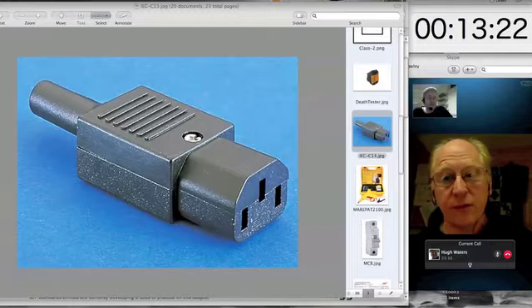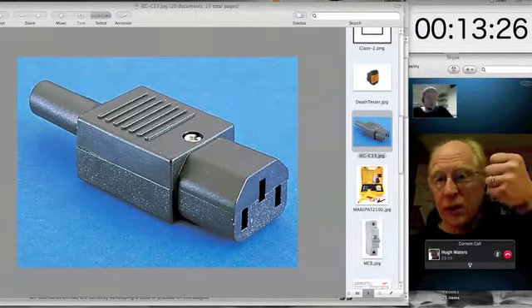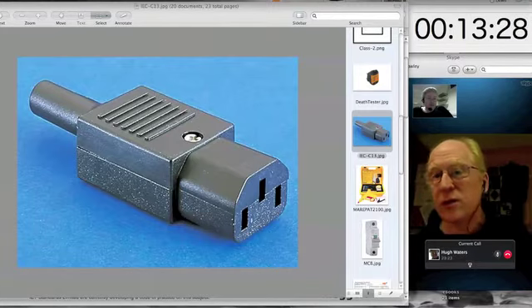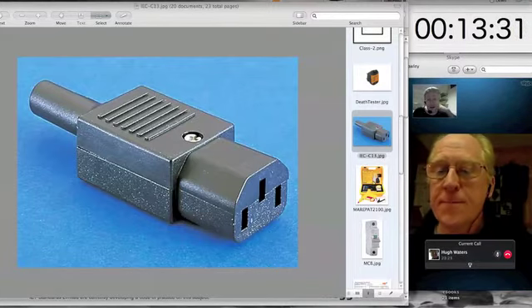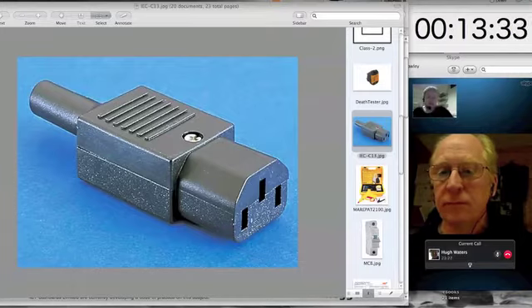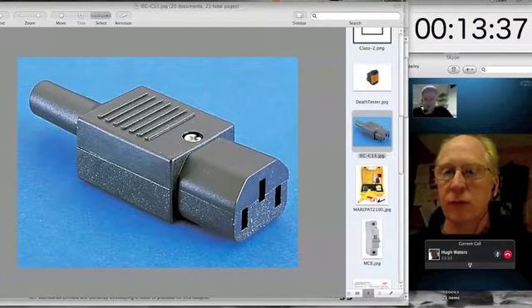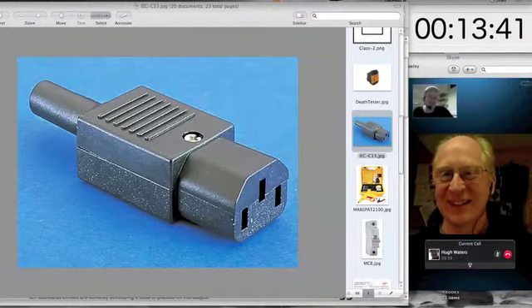Do they have MCBs to the bus bars, or do they still have those enormous fuses? They used to have one on each phase. Yeah, so if you can consider 3 200 amp phases coming into a facility, which is very typical. Of course, nowadays, where we don't tend to have big lighting gantries anymore, for the little studio, and air conditioning requirements are a lot more modest, and all those kind of things.